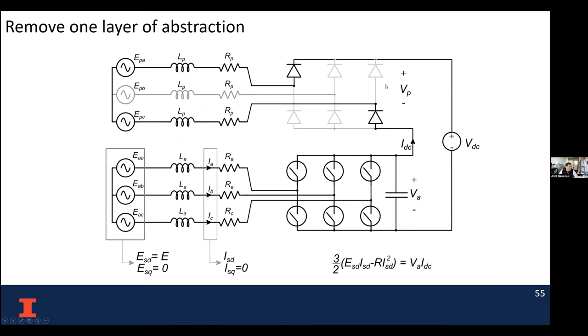Let's remove one layer of abstraction for a second and see how we can solve this. These are AC sources, the windings producing AC voltages with their own parameters. For simplicity, let's consider one passive port and one active port. If we can control the active rectifier current here, and if I'm maintaining the DC bus voltage, I can control the DC bus current. If I can control the DC bus current, then depending on the voltage, the diodes turn on accordingly, and we can control the current on the diode bus. That's the essence: even though we have so many passive rectifiers, we can still achieve power flow control. Still, this architecture looks complex.